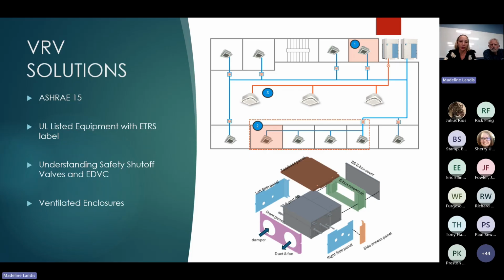When you are doing your calculations and your designs at the beginning, it's important to do the EDVC calculations for each of the rooms that's associated with those valves. And in the worst case scenario, if you are above that RCL limit for one of the small spaces, then you can look at using a UL listed ventilated enclosure for our branch selector boxes.